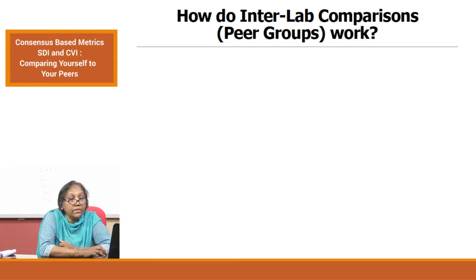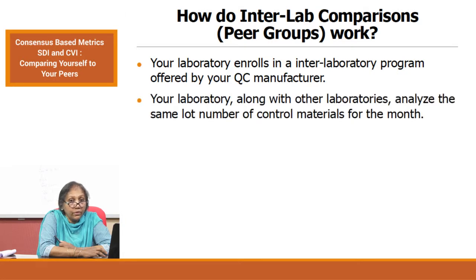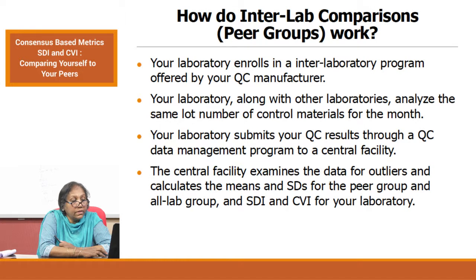How do inter-lab comparison peer groups work? Your laboratory enrolls in the inter-laboratory program offered by your QC manufacturer. Your laboratory, along with other laboratories, analyzes the same lot number of control materials for a month. Your laboratory submits your QC results through the QC data management program to a central facility. The central facility examines the data for outliers and calculates the means and standard deviation for the peer group and all lab groups.